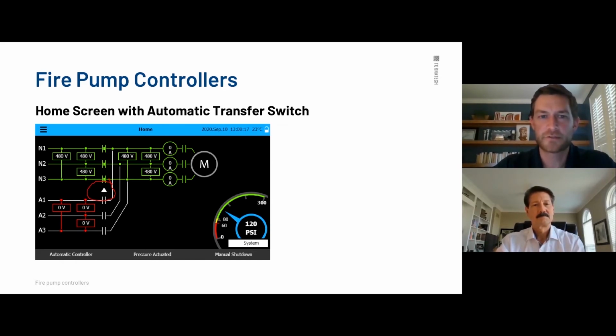So there's actually a lot of ways that you can see where it's running. But when the transfer switch is on, you'll have voltage here from the generator. That triangle will be upside down, and these contacts that are closed right now will be opened, and these will be closed. So you'll be able to flow, and then these lines will be green, and it just shows the flow of electricity coming from the generator side.